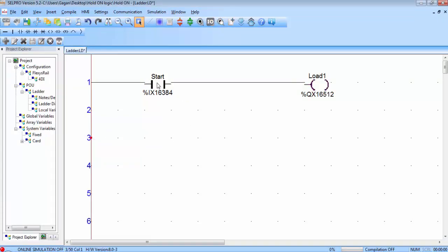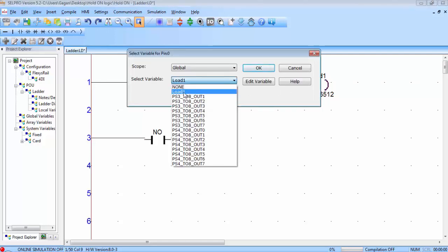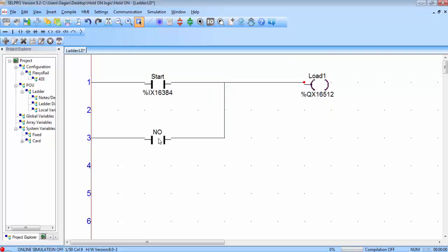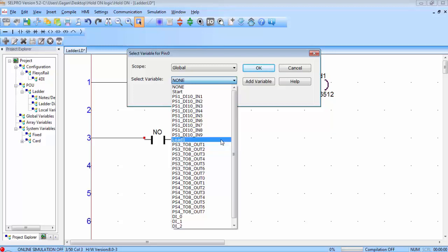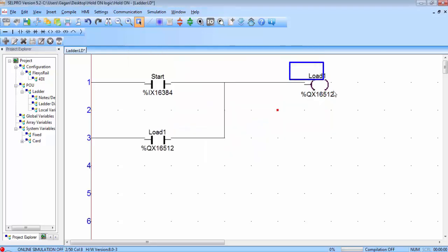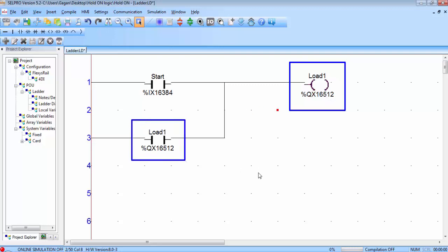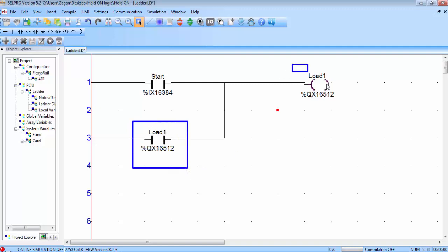I will place one parallel contact next to the NO contact. The concept is that you can assign the output address to an input contact. The output address is OUT0 — load1 is OUT0 from PS3, which is card number 3. Double click on the parallel contact, click on Select Variable, and assign the load1 address to it. Now the output coil address is the same as the address of this NO contact, so the status of this contact depends on the status of the coil — if the coil is ON, this open contact becomes a closed contact.